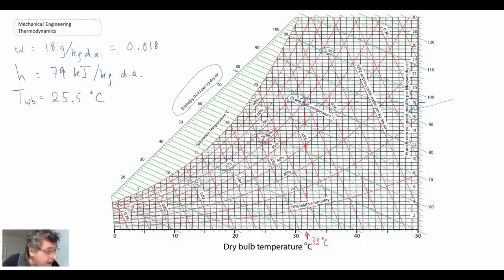And the next thing they want is the dew point. The dew point is the temperature at which water starts to drop out. So we're lowering the temperature, lowering the temperature, and then we get to the saturation point where water starts dropping out. That's when you get condensation, moisture, dew forming, you know, on a morning on your car for example. So in order to get that, we're not changing the specific humidity, but in order to get dew point, we're dropping the dry bulb temperature. So for that, what we do is we move directly to the left and we get to this point here, and we then go down to read the temperature for that. And so that comes out down here—so that's 21, 22, 23. I would say the dew point temperature then is about 23 degrees C.